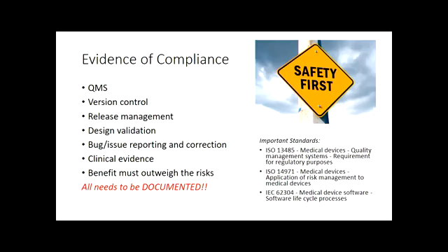And the trick is to document all of this. There are a few very important standards when it comes to medical devices incorporating software. It's the standard ISO 13485. Then it's the risk assessment management standard, ISO 14971. And the new one is the medical device software lifecycle processes standard, IEC 62304.